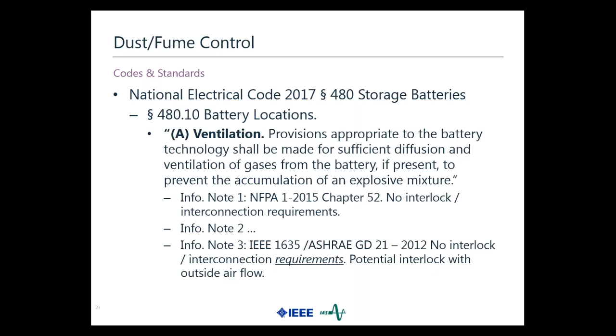Non-code issues - we touched on distribution ductwork and air vent location. Something you may not think about is whether you need independent AFD (adjustable frequency drive) cooling for your drives. A lot of times that'll be on the medium voltage, but it's possible to have a rather large low voltage AFD that requires special cooling.